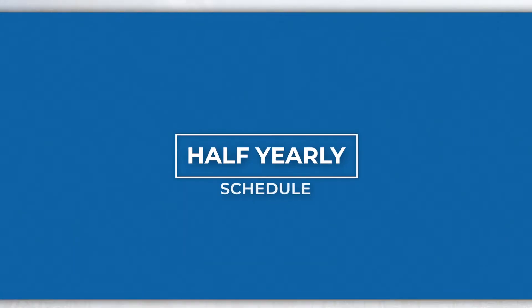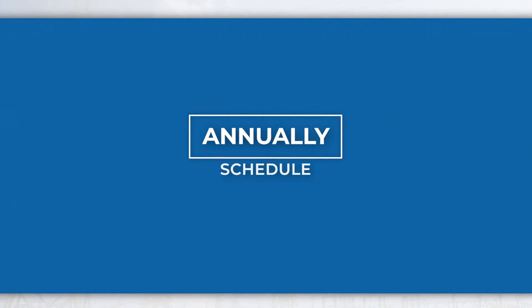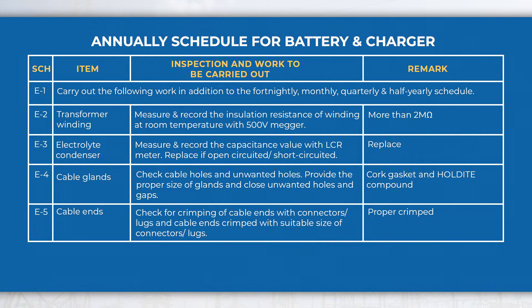In the half-yearly schedule, perform activities like checking the working of the rectifier, coarse fine control switch, and trickle boost changeover switch, etc., in addition to fortnightly, monthly, and quarterly schedule activities. In the annual schedule, perform activities like measuring the insulation resistance of transformer winding and capacitance of electrolyte condenser, etc., in addition to fortnightly, monthly, quarterly, and half-yearly schedule activities.